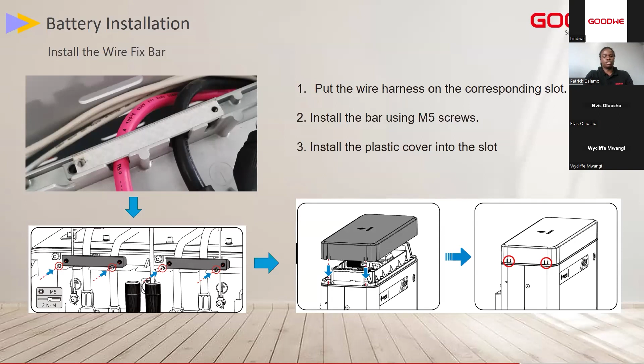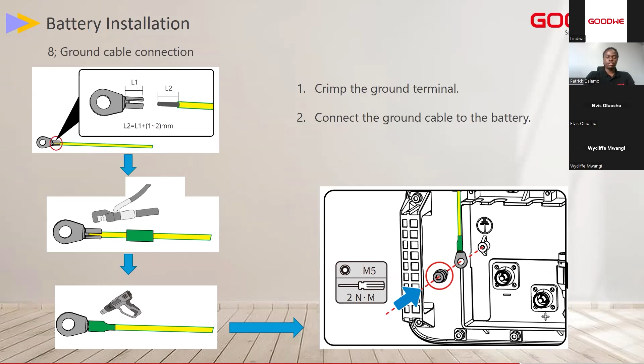The whole installation will be neat and clean, easy to display with no need to hide anything. One important installation requirement is to ground your battery. On the top part of the battery, where all terminations are done in one phase, your grounding cable will also be terminated at the top side in the cover. Fix this before switching on the battery or inverter, before commissioning. Ground your battery, ground your inverter, ensure all are in a levelized grounding system. Once you install the cover, the installation becomes neat.